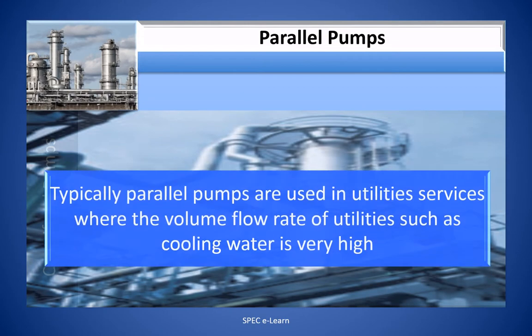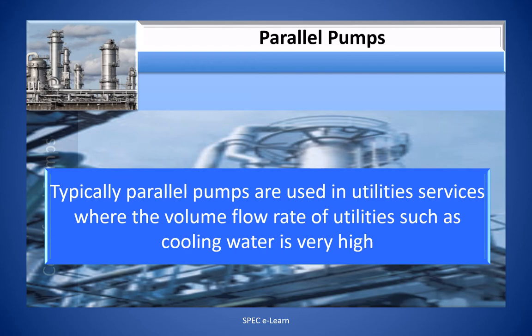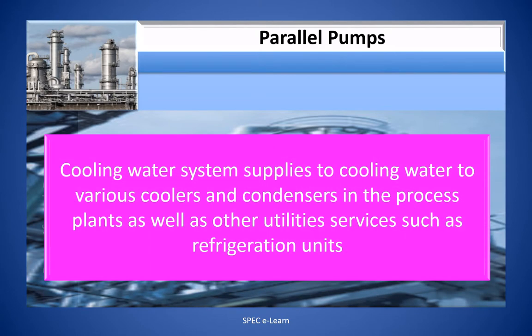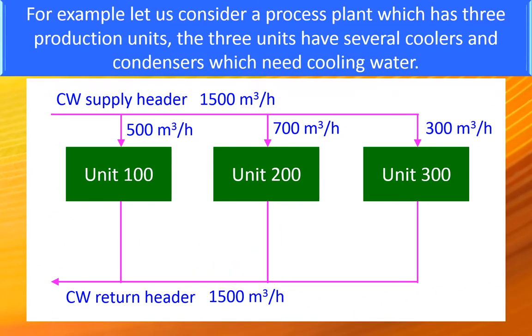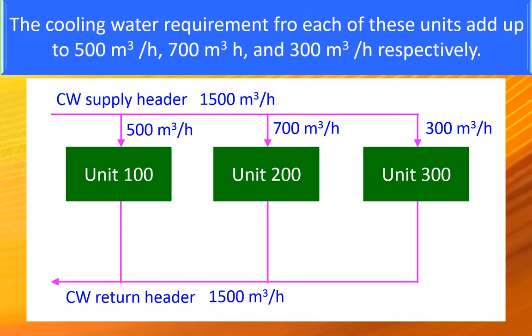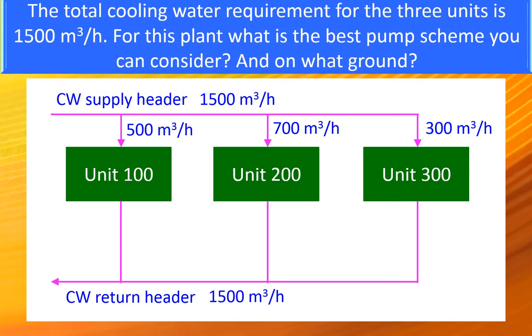Typically, parallel pumps are used in utility services where the volume flow rate of utility such as cooling water is very high. Cooling water system supplies cooling water to various coolers and condensers in the process plants as well as other utility services such as refrigeration units. For example, let us consider a process plant which has three production units. The three units have several coolers and condensers which need cooling water. The cooling water requirement for each of these units add up to 500 cubic meter per hour, 700 cubic meter per hour and 300 cubic meter per hour respectively. The total cooling water requirement for the three units is 1,500 cubic meter per hour.